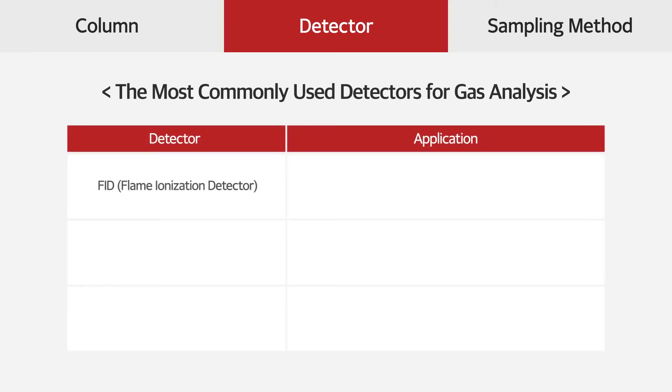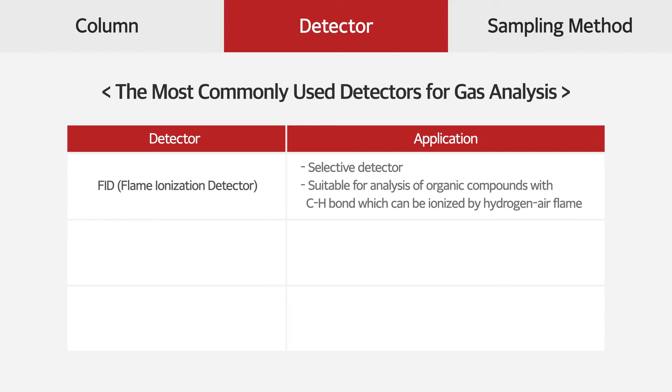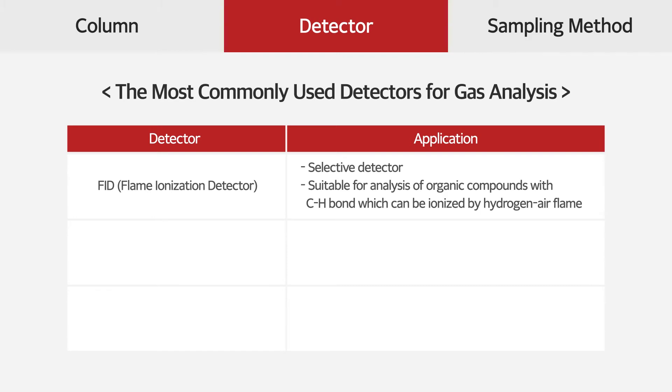The FID is the most commonly used detector in GC analysis, and it selectively detects organic compounds, including CH bond, which can be ionized by hydrogen air flame. It also detects low level of carbon monoxide or carbon dioxide by converting them into methane with the methanizer.